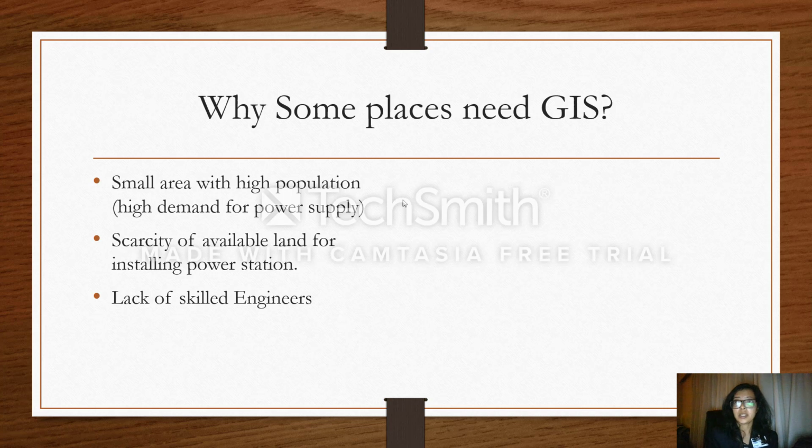In my workplace, I mostly dealt with GIS because I came from Dhaka, which is a small area with large population, and the demands are increasing every day. We need to make more substation, but we don't have much area. So either we are going underground or maybe at the first floor or second floor of a multi-story building. For safety of the people there, we need to use something that is safer than other options. So GIS was the best option for us, and also we don't have much skilled workers to maintain this. Maintain the environment and maintain safety. So GIS was best for us in every way. So most of our newest substations are GIS, and in older substations, the older switchgears are replaced by the GIS switchgears.